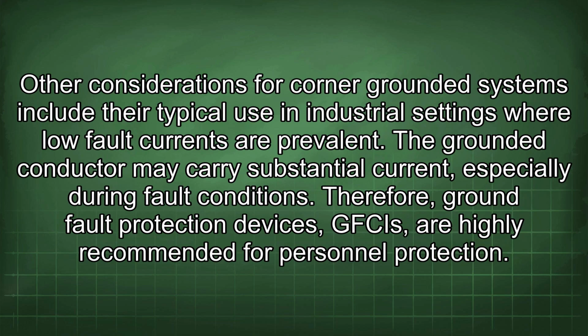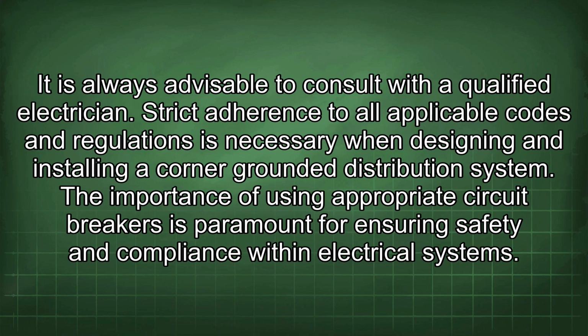Other considerations for corner-grounded systems include their typical use in industrial settings where low fault currents are prevalent. The grounded conductor may carry substantial current, especially during fault conditions. Therefore, ground fault protection devices, GFCIs, are highly recommended for personnel protection. It is always advisable to consult with a qualified electrician. Strict adherence to all applicable codes and regulations is necessary when designing and installing a corner-grounded distribution system.